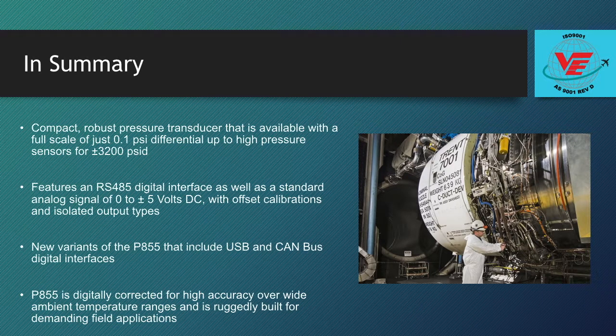In summary, the P855 is a compact, robust pressure transducer that is available in a wide variety of pressure ranges, from units with a full scale of just 0.1 psi differential up to high pressure sensors for plus and minus 3,200 psid. The P855 features an RS485 digital interface as well as a standard analog signal of 0 to plus or minus 5 volts DC, with offset calibrations and isolated output types. In addition, there are new variants that can include USB and CAN bus digital interfaces. The compact P855 is digitally corrected for high accuracy over wide ambient temperature ranges and is ruggedly built for demanding field applications.